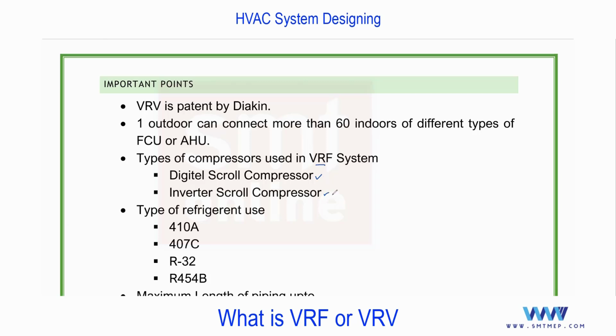So the digital compressor concept is that it uses engage and disengage as per the load requirement. But the type is scroll only. With an inverter scroll compressor, you'll find variation in speed. The inverter scroll compressor can run at different speeds because it works with a VFD drive. So what is VFD?